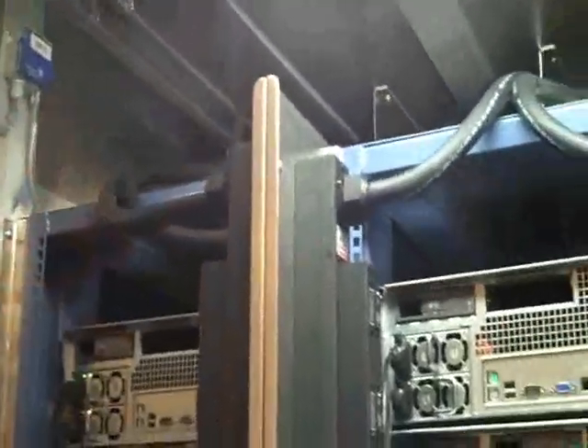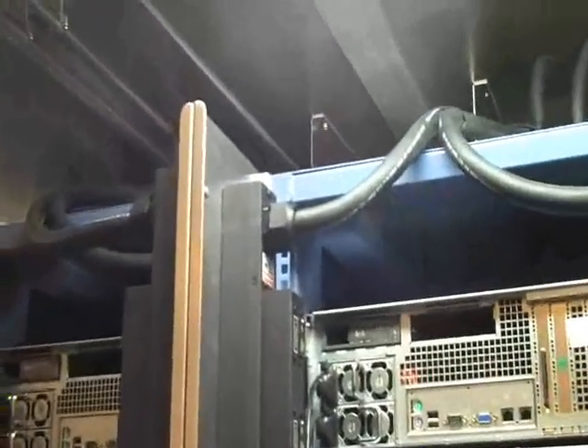And again, the production unit has a much larger hot aisle, so you have an actual hallway here. You can see that we're bringing in power to the racks. This is standard, what anybody in the data center business would see as standard four-post racks. We bring in 400 to 415 at 30 amps times two for redundancy. And we have an A and a B bus bar that's above here that they connect to.